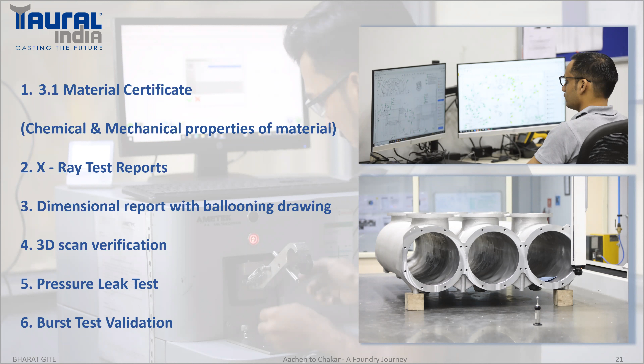All these castings in their substations contain SF6 gas at 7 bar continuously throughout their life. So what we need to provide, in general, is the material certificate for chemical and mechanical properties, X-ray test reports, dimensional reports with the ballooning diagram—as this colleague is doing the ballooning diagram—3D scan verification, pressure leak test, and burst test. The burst test is something we will talk about in further slides.